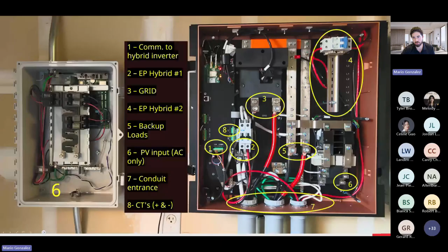All right, so now the gateway. This is the gateway and how it looks once everything's installed. Number 1, this is the communications. Very important. This is the communication cable, the 33 feet long one that comes with factory. Very important. Whenever you do this, take your time. Make sure that these line up. There's been a number of times installers rush through everything and the system doesn't back up properly, or there's a communication issue, and it's always because of this little guy over here.